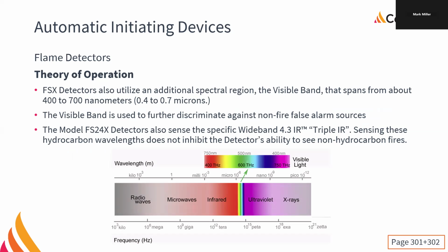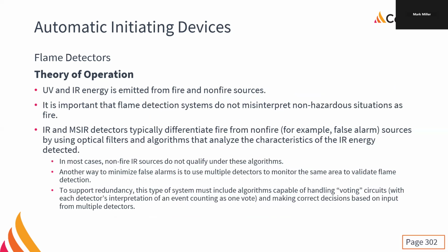So we're looking at either the infrared or the ultraviolet range. So we're also going to be picking up across the visible band. So this is a very narrow range of wavelengths. One of the reasons that we are detecting across the visible range is we want to be able to discriminate against non-fire, the false alarm sources. Our UV and IR energy is emitted from both fire and non-fire sources. We do not want to get confused. We do not want misinterpretations.